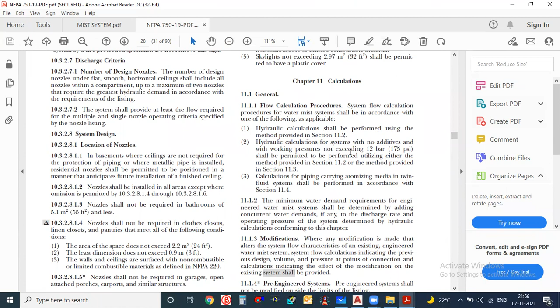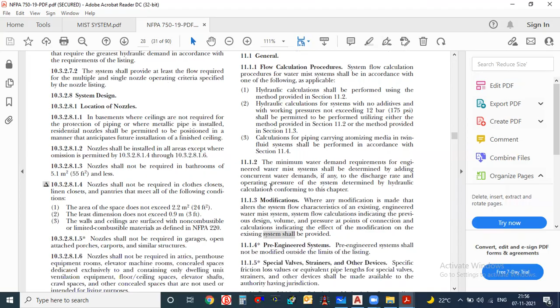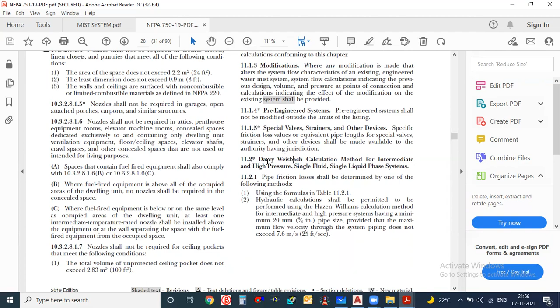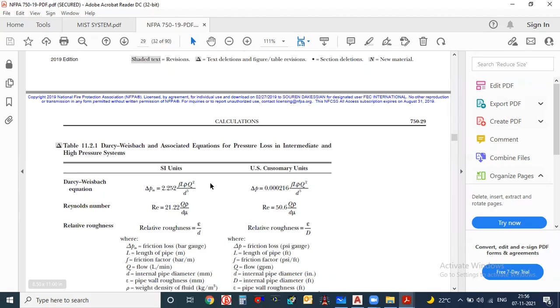So maybe one section is given here. Hydraulic calculation for a system with no additive will be permitted to be performed. Okay, some things are given here, so let us see what method they have given. If you go a little bit down here, you will see one method they have given, the Darcy-Weisbach calculation method. Here they have given it for systems whose pressure is greater than 12 bar or 175 psi. They are telling us to follow this method, Darcy-Weisbach, and some formulas are given here.